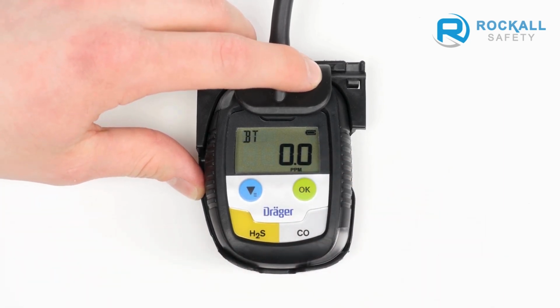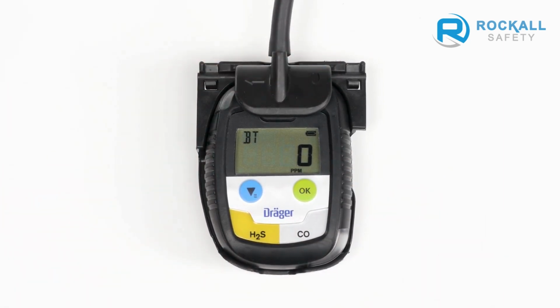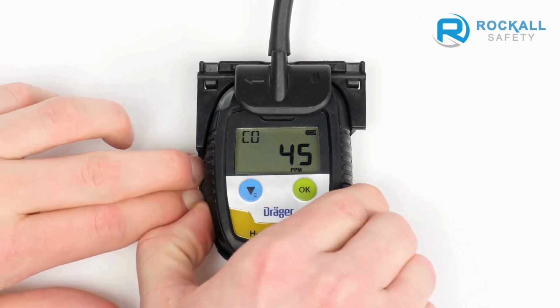The BT symbol will appear on the display for the current bump test. After a few seconds, the Dräger Pac will activate the alarm. Remove the device from the calibration adapter. As soon as the bump test is completed, the alarm stops and OK will appear on the display of the device.